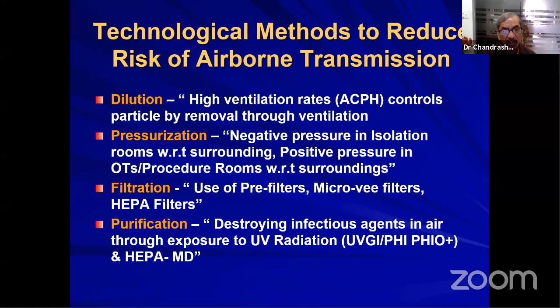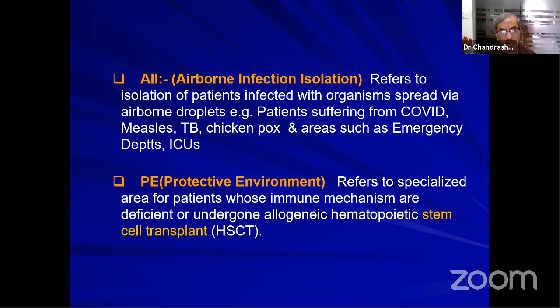In the airborne infection isolation, I will be talking about this only: patients infected with organisms spread via airborne droplets. So this is COVID, measles, TB, chickenpox, etc. Generally, we have been using it for TB patients as of now. Now it has become mandatory for all of them. This is a negative pressure isolation, or AII, where air should flow from the corridor to the isolation room to prevent contamination. An anteroom provides an airlock between the room and corridor, maintains continuous negative pressure, and a separate exhaust system is placed to remove at least 15% more air than the inlet.